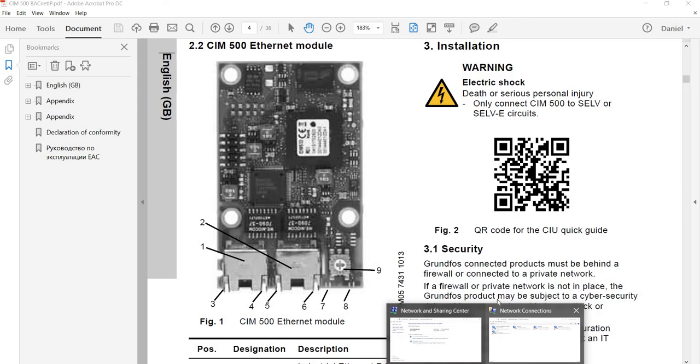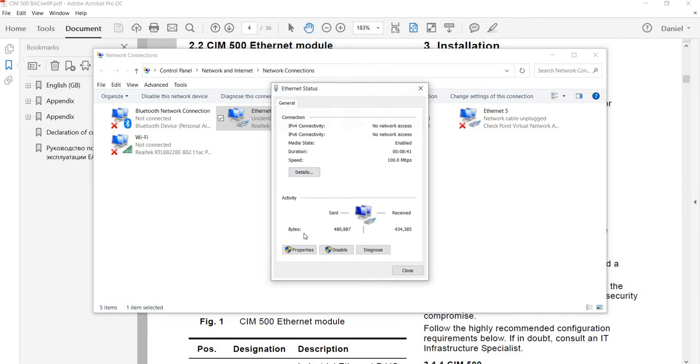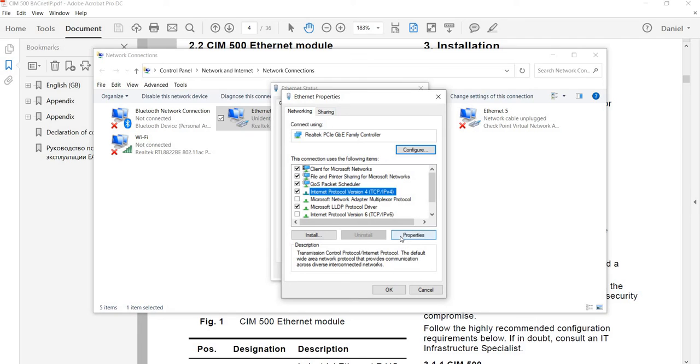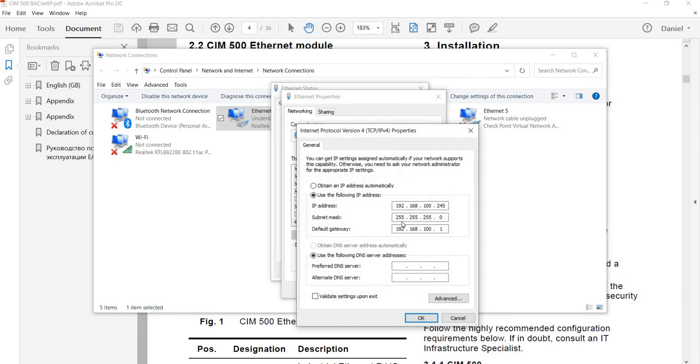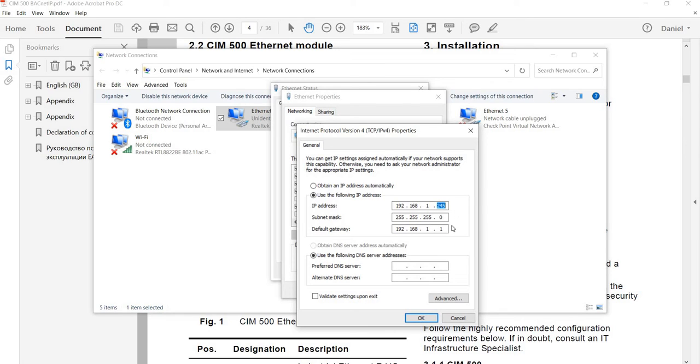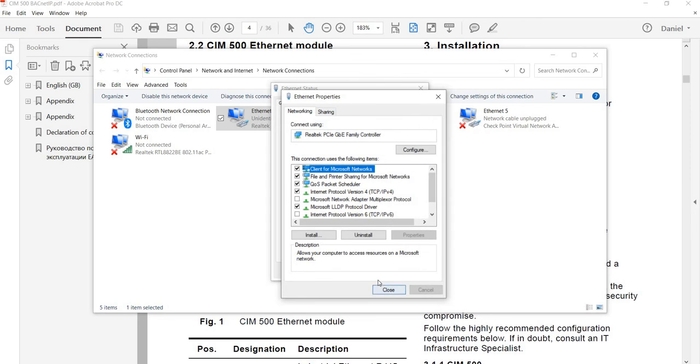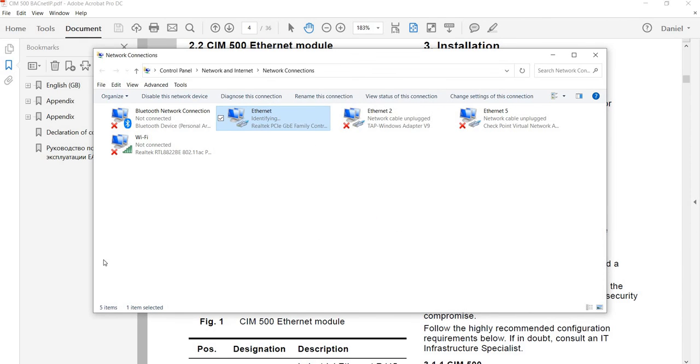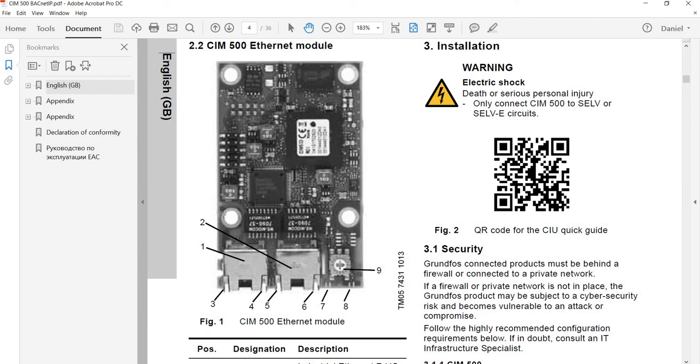Okay, so got to get ourselves on the right network here so we can talk to this thing. So the first thing is IPv4 settings. I'm on the 100 because that's our BACnet network. Change that to 1. And I've got 245 here, so I'm not going to conflict with the IP address of the CIM500 card. Hit okay, close this out to make the changes take effect. That one got me yesterday. And now I'm going to walk over to the pump and connect my ethernet to the pump.